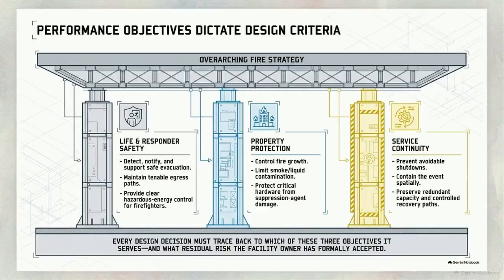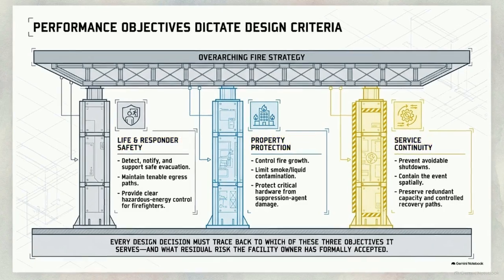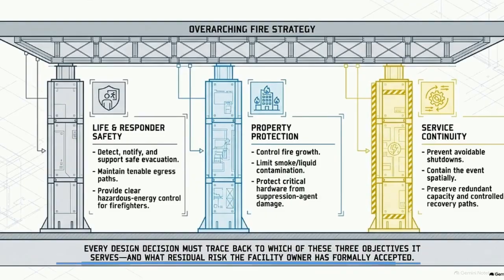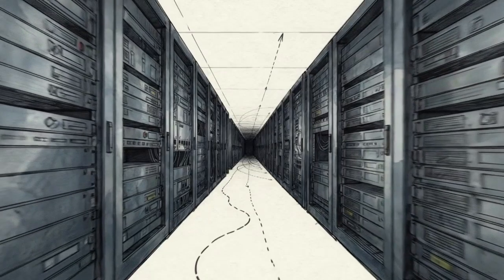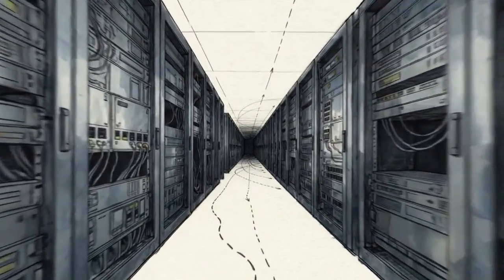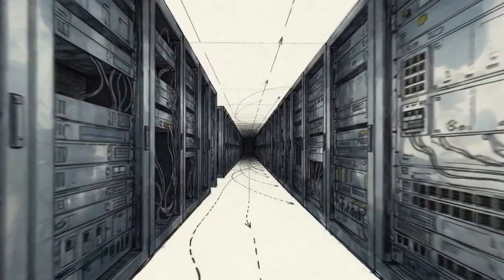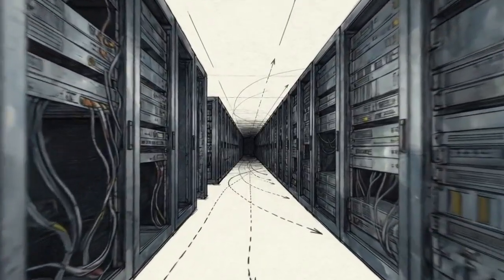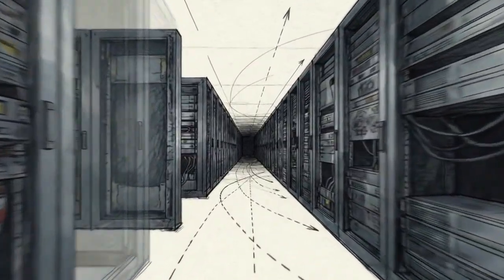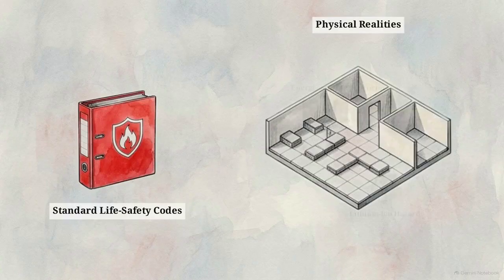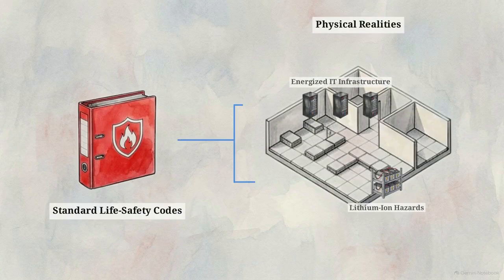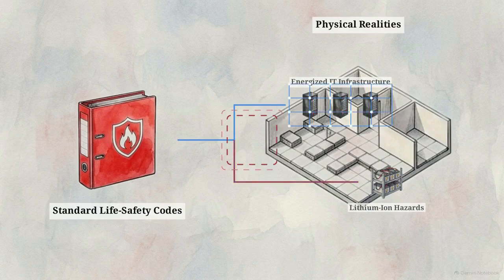This chart shows every design decision maps back to three overarching objectives: life and responder safety, property protection, and service continuity. These goals often conflict. The owner must explicitly define the residual risk accepted for each pillar. Undocumented or ambiguous protection logic creates hidden failure points that lead directly to the top event: a catastrophic loss of critical IT service.